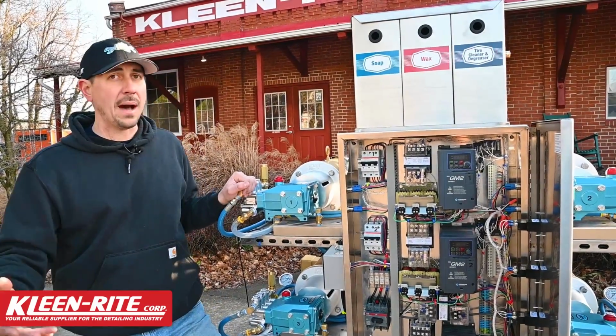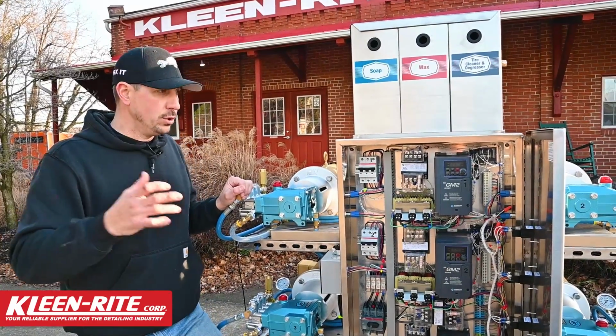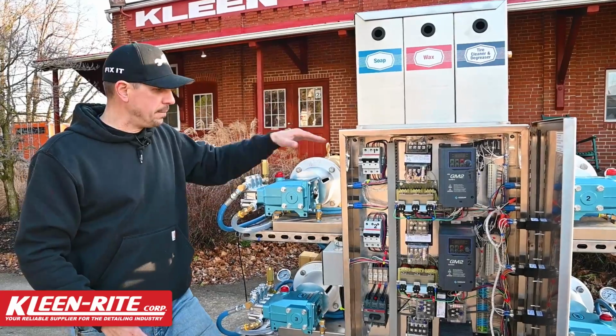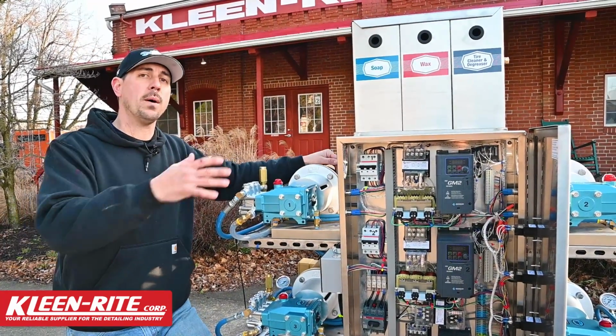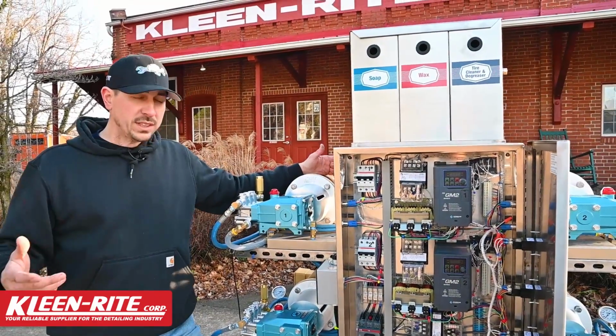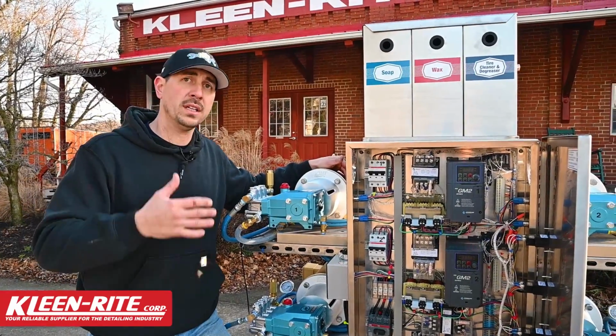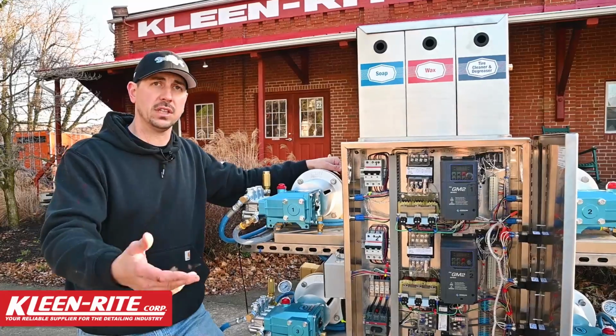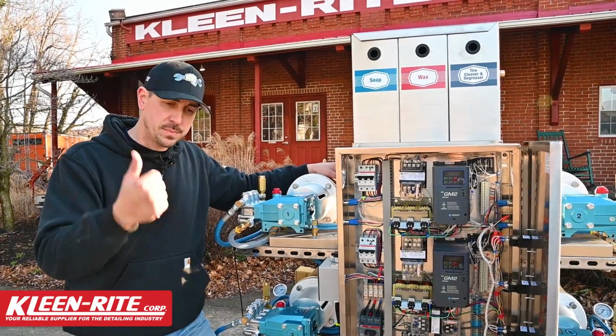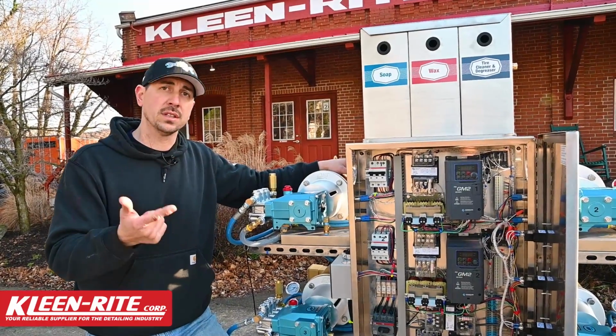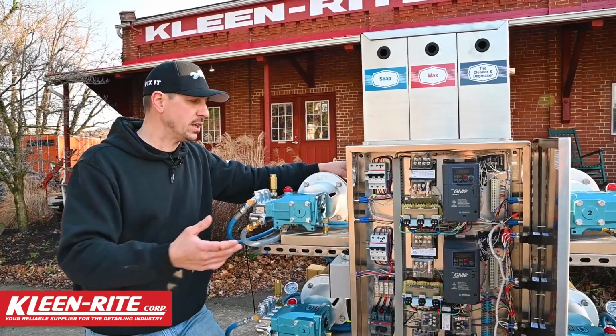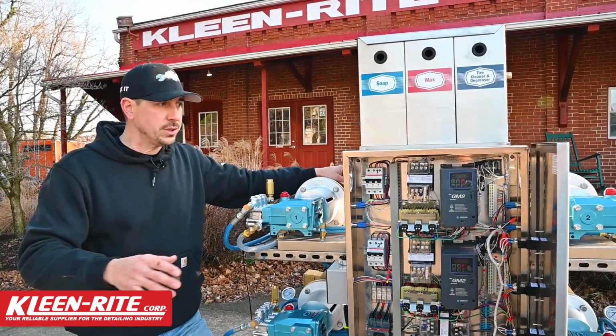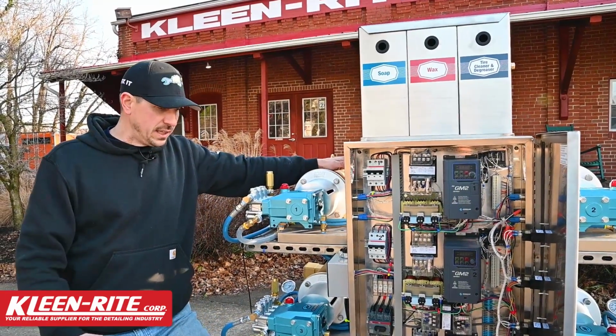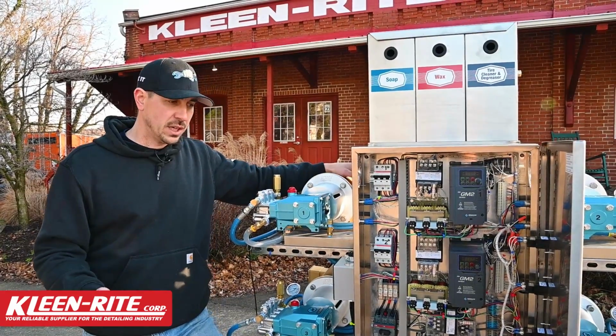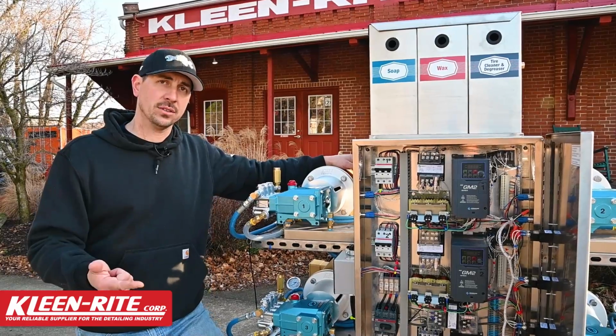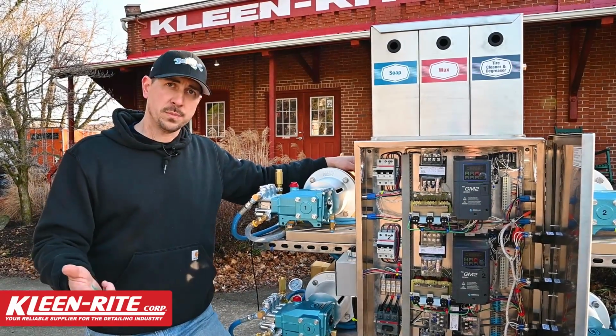right away. Now on top of that, the benefit is we can use the VFD to control this pump and motor to give us the availability to dictate what pressure we want to run out of this pump. What does that mean for us as operators? That means we're able to run less equipment. And what I mean by that is all the auxiliary equipment that you have, like spot-free delivery units or low-pressure delivery units, all of those things are now not needed because we're doing it all through one pump. And we're able to do that, again, because of the VFD. The VFD is going to save us in electrical consumption, wear and tear, parts, and downtime, and on space in the equipment room.